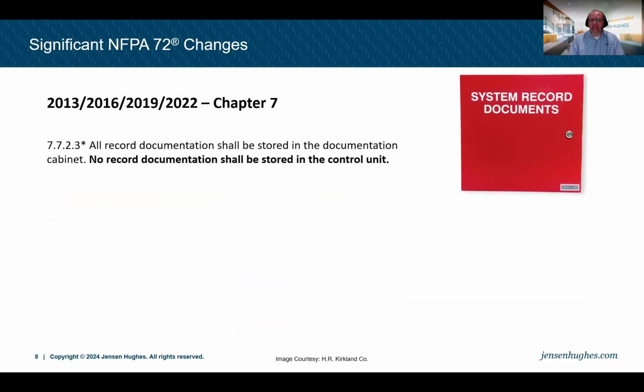Now, let's look at some of the installation changes that have been made in that same 2018 to 2024 time period that might be interesting to you as a facility manager. The first one deals with documentation and what kind of documentation you keep at your local facility for your fire alarm system. As of the 2013 edition, we had record documentation cabinets required for all fire alarm systems. It says that all record documentation shall be stored in a documentation cabinet and that no record documentation be stored in the control unit. Now, if you go to your facility, maybe even today, and open up that fire panel, you'll probably see papers and all kinds of things stuffed in there. Well, that's actually against the installation standard of NFPA 72. There should be no paper, no storage inside a fire alarm control unit whatsoever.